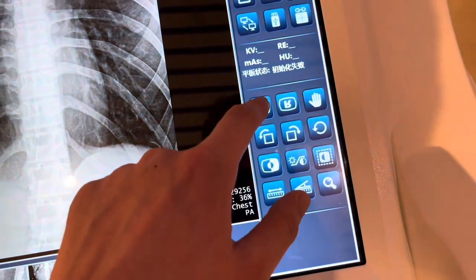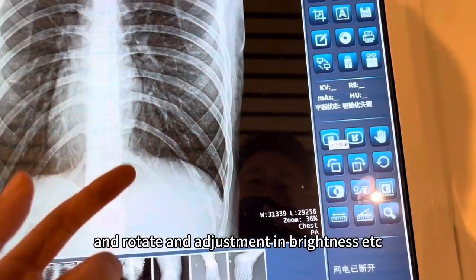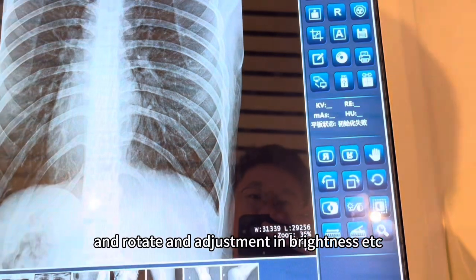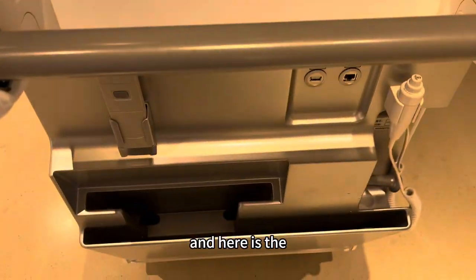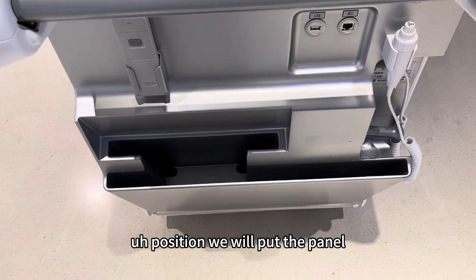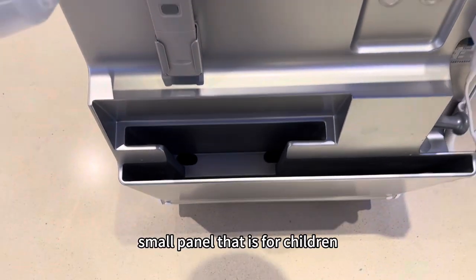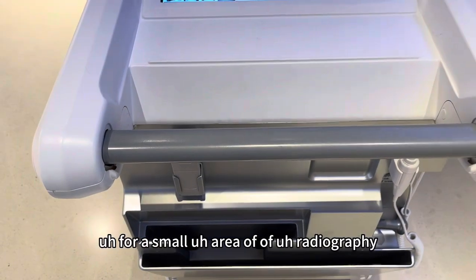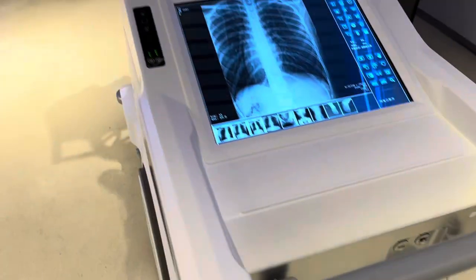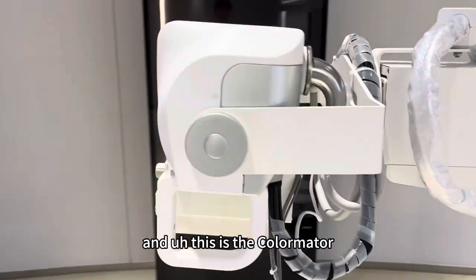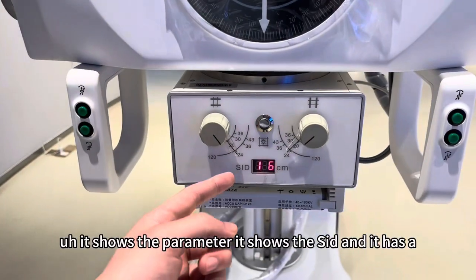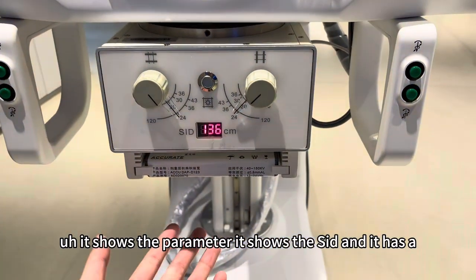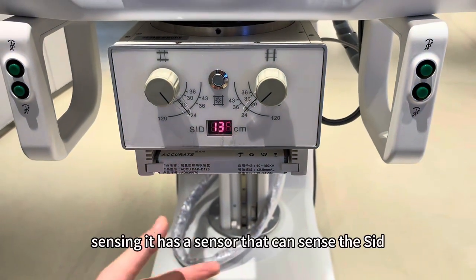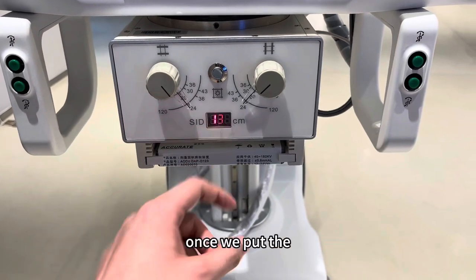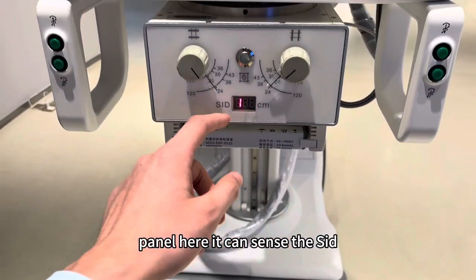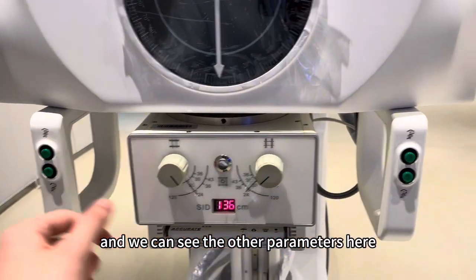and rotate, and adjustment in brightness, etc. And here is the position where we put the panel, and there's a slot for a small panel that is for children, for a small area of radiography. And this is the collimator. It shows the parameter, it shows the SID, and it has an automatic sensing. It has a sensor that can sense the SID. Once we put the panel here, it can sense the SID, and we can see the other parameters here.